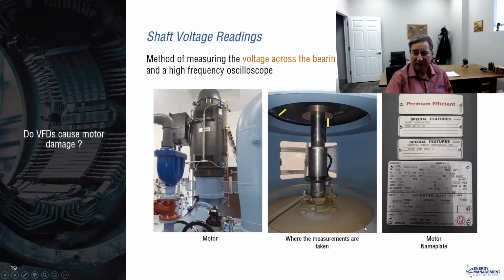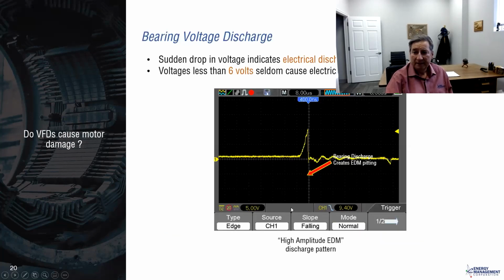And this is, I think, a 1,000 horsepower vertical motor. So here's what you'd see when you have an oscilloscope. You have to have an oscilloscope to capture these waveforms. But you see a buildup of voltage and then a complete discharge of voltage. That's how you know that you've got this bearing current issue, that you see that rapid collapse and overshoot. And that's what starts to cause the electrostatic pitting that we'll see in a few others.